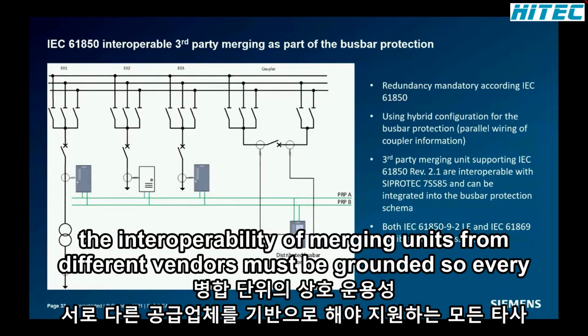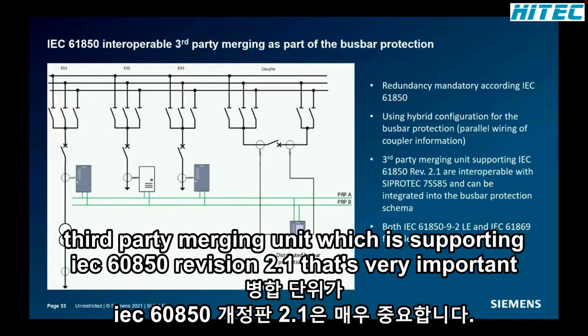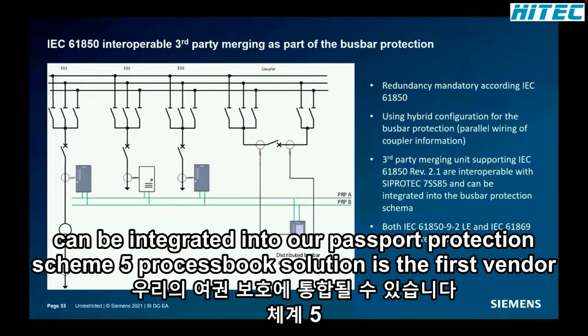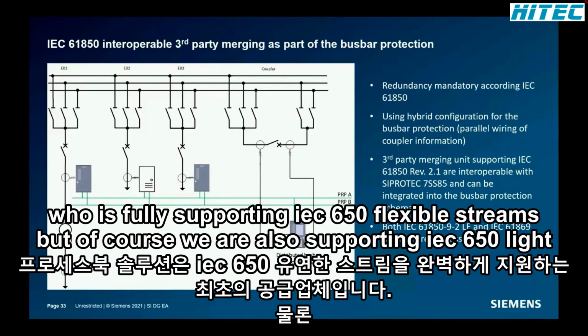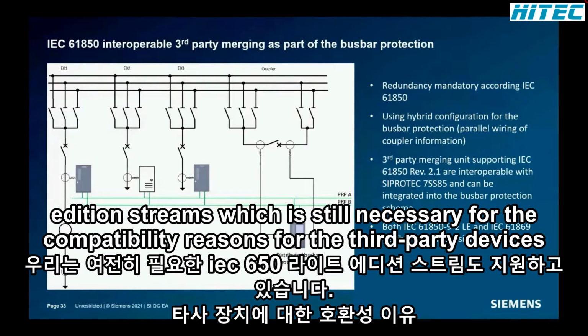So every third-party merging unit which is supporting IEC 61850 revision 2.1, that's very important, can be integrated into our busbar protection scheme. The SIPROTEC 5 process bus solution is the first vendor solution fully supporting IEC 61850 flexible streams. But of course, we are also supporting IEC 61850-9-2 light edition streams, which is still necessary for compatibility reasons with third-party devices.